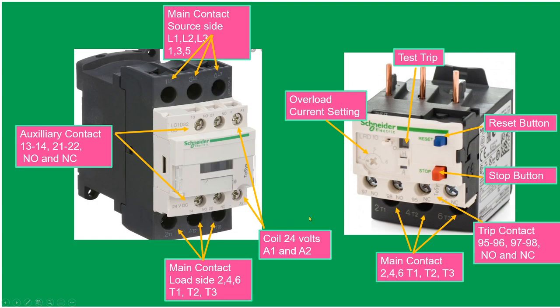This is the coil, 24 volts, A1 and A2. If we put a source here, the plunger will move down, passing current from line one to T1. Next, auxiliary contacts: we have 13 and 14, and 21 and 22. We have normally open and normally closed.